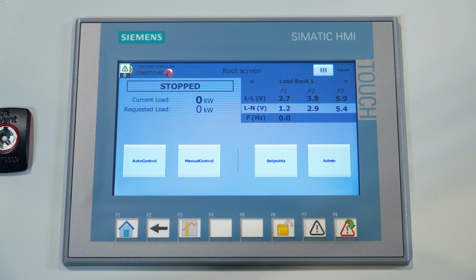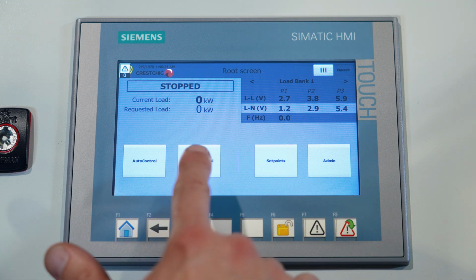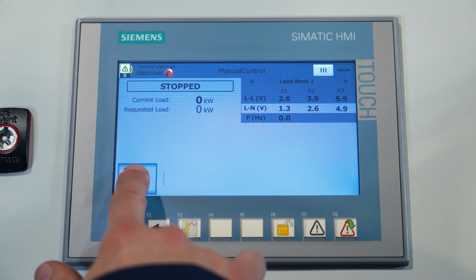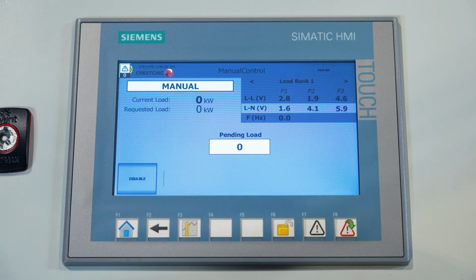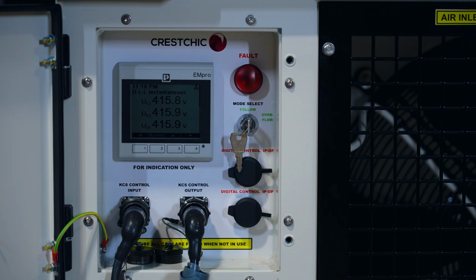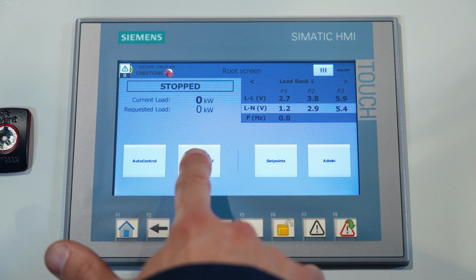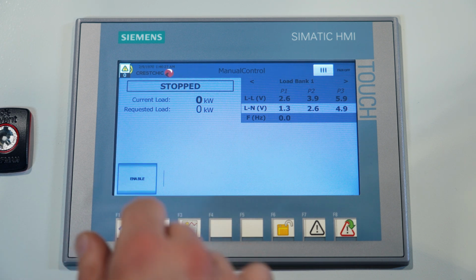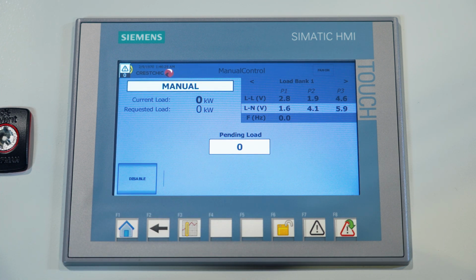The following is different to the KCS control, where the load banks are started from the digital controller rather than the start and stop buttons on the load banks. We can now switch on the power to the digital controller and switch on the load supply to the load banks. Once this is present, it is possible to see the voltage on the load bank's instrumentation meter and on the digital controller. Once the digital controller has booted up, we can choose between 2 different modes to apply load.